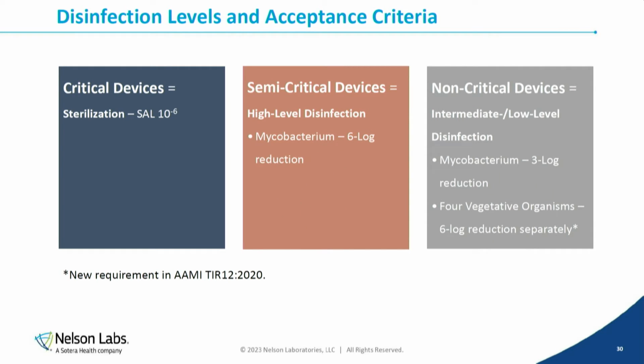Now for disinfection levels, we have critical devices that need sterilization. There's no disinfection for that, okay? If you have a critical device and you're saying, well, we have to figure out a way to disinfect them, that's not going to work with regulations. You will have to do sterilization. If you can't do steam, it's going to be low temperature sterilization modalities, like VHP. EO is not for reusable devices because it's a fast-paced environment and we have to wait for residuals. It doesn't work that well for us. But VHP is the next standard next to it.